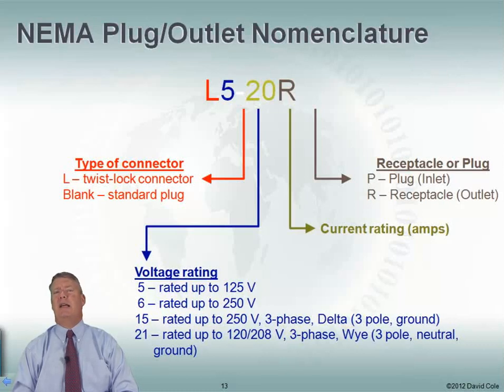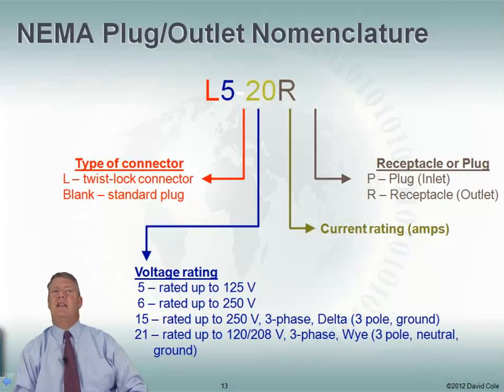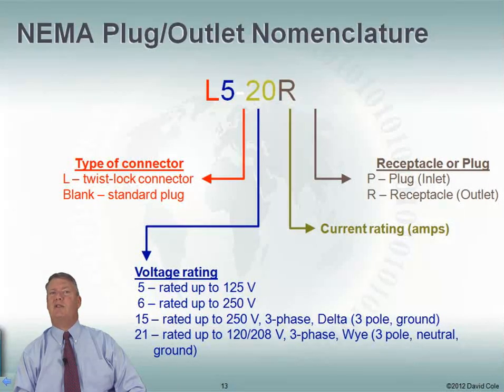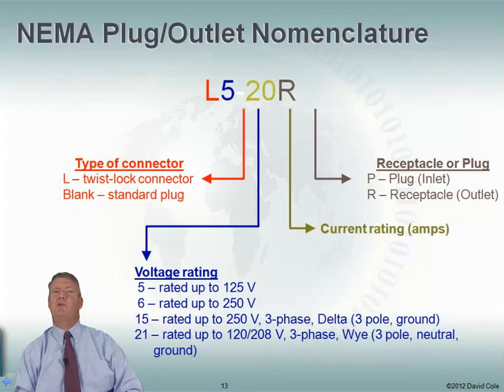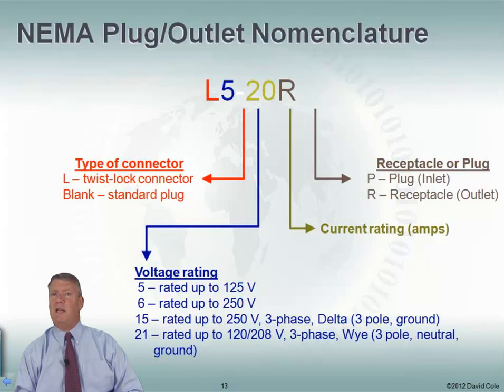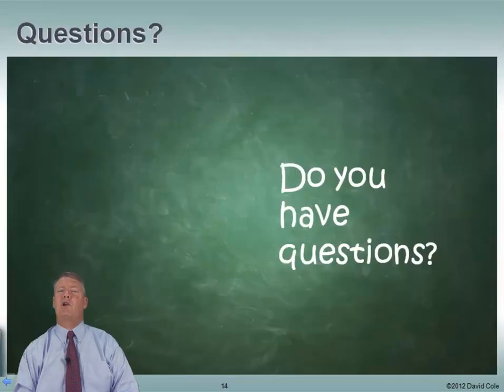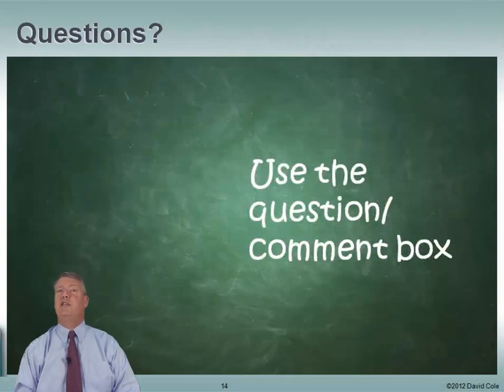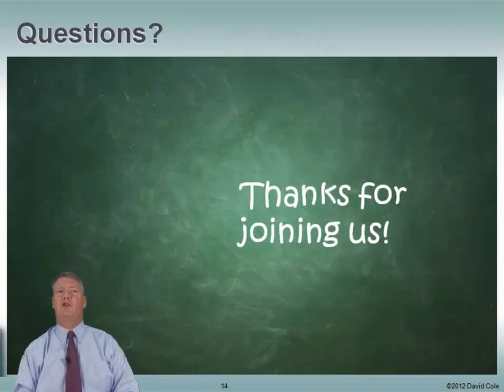The NEMA plug and outlet nomenclature — this is really more for reference. When buying plugs or outlets, this is how NEMA defines them. The first character is the connector type: L means it's a twist-lock connector, a blank means it's a standard plug. The 5 is the voltage rating — in this case, rated up to 125 volts. The 20 is the current rating, supporting 20 amps. Finally, R means it's a receptacle (an outlet), and P means it's a plug. So we've talked about circuit breakers and the NEMA nomenclature. If you have any questions, please use the question and comment box. Thank you very much for joining us — I look forward to having you at the next module.